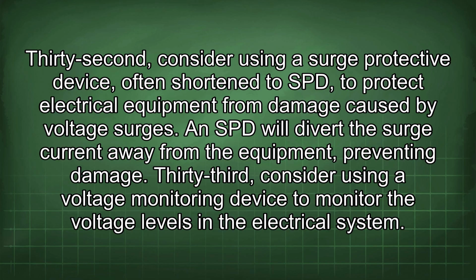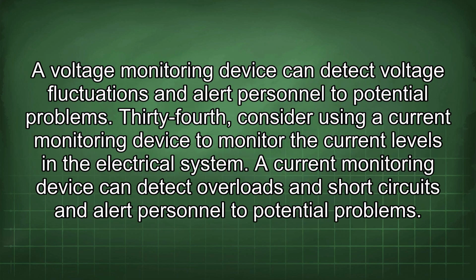32nd, consider using a surge protective device, often shortened to SPD, to protect electrical equipment from damage caused by voltage surges. An SPD will divert the surge current away from the equipment, preventing damage. 33rd, consider using a voltage monitoring device to monitor the voltage levels in the electrical system. A voltage monitoring device can detect voltage fluctuations and alert personnel to potential problems.